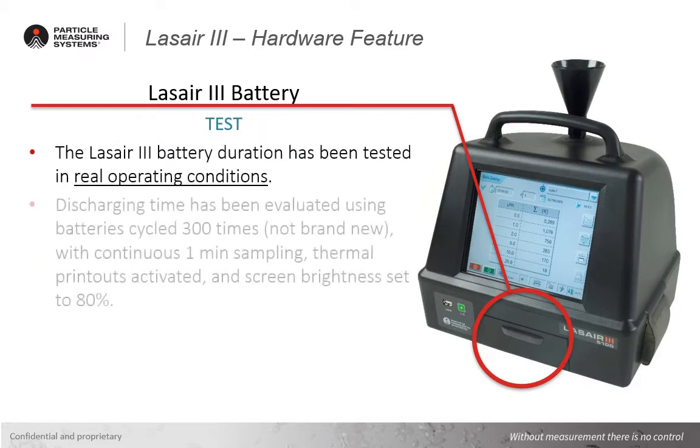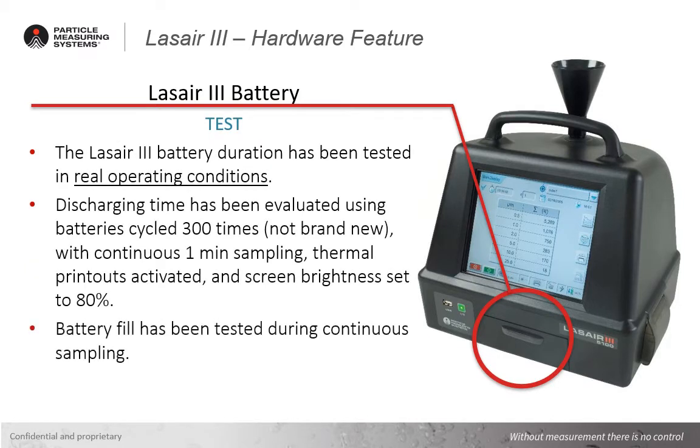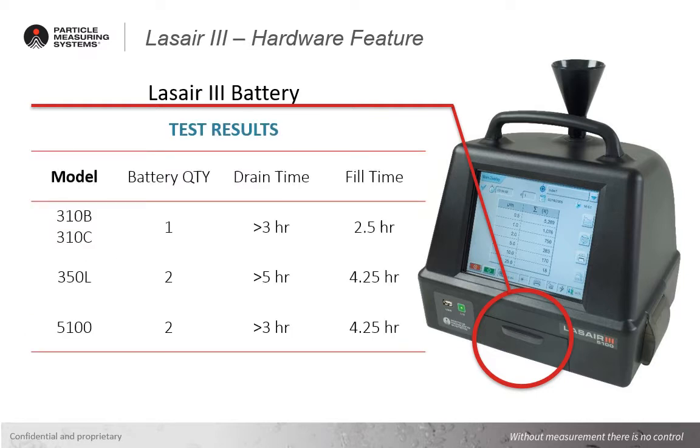The new lithium-ion battery within the Lasair III has been run through a large range of testing for real-world operational conditions, and has proven to be robust and reliable over hundreds of charging cycles. The discharge rates were performed with batteries with over 300 charge cycles, and the instruments in a typical configuration, with one-minute samples and thermal printouts being generated, and the screen brightness set to a typical 80%. The results of the testing can be seen below in the chart.